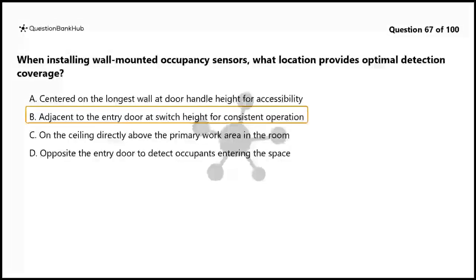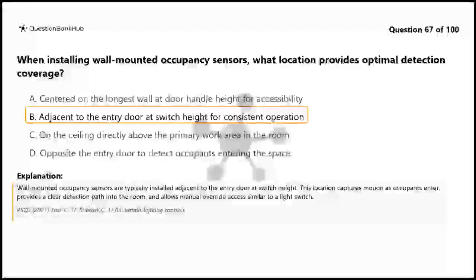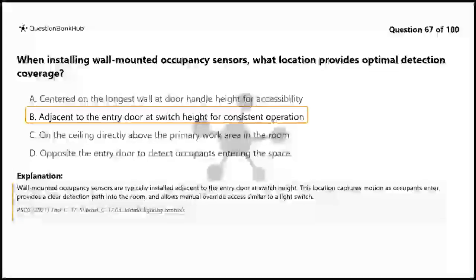The correct answer is B. Adjacent to the entry door at switch height for consistent operation. Wall-mounted occupancy sensors are typically installed adjacent to the entry door at switch height. This location captures motion as occupants enter, provides a clear detection path into the room, and allows manual override access similar to a light switch.